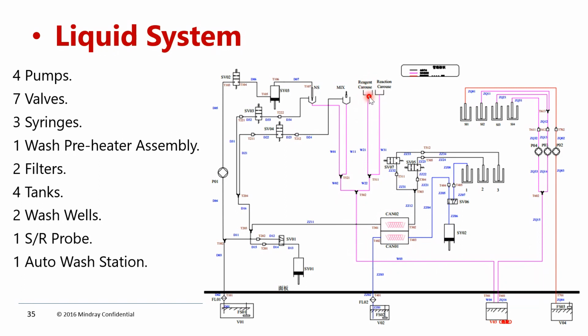So here we have a line, because this line is for condensation water. Since we are maintaining 2 to 12 degrees in the instrument's reagent compartment, there will be condensation water. That condensation water will go through the waste line, and simultaneously, from the reaction carousel, if any cuvette overflow happens, that water also exits through this line. Okay, this is a diluted waste tank.